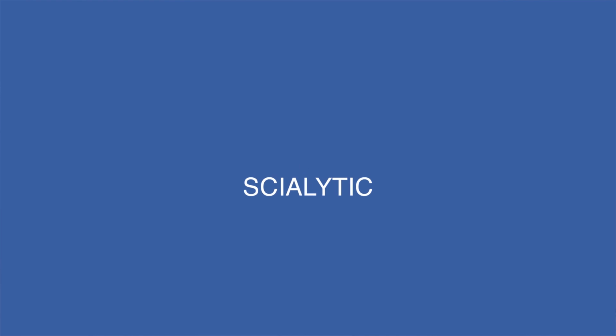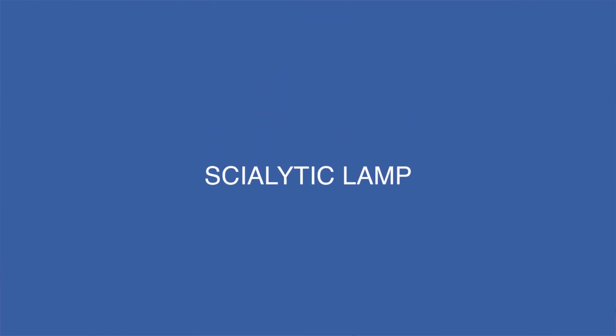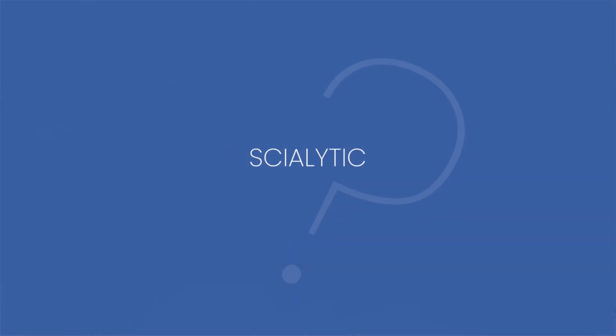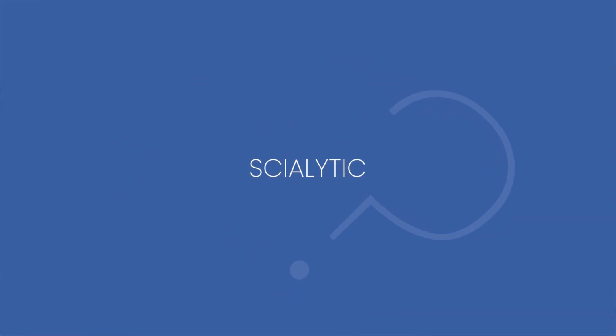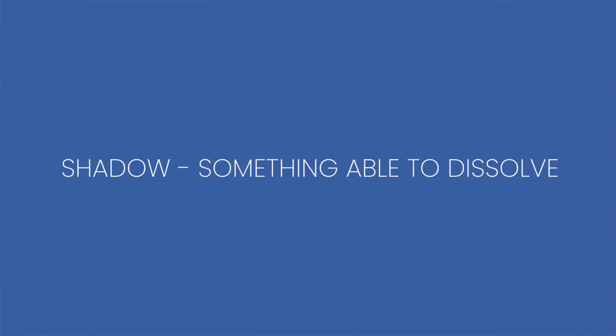Before addressing the history, however, I will allow myself an etymological analysis on the meaning of scialytic, because we refer to lamps as scialytic lamps, but what does scialytic mean? Scialytic is a compound word, made of skia and litikos. Skia is the Greek word for shadow, while litikos describes the ability to dissolve something. Putting them together, scialytikos identifies something capable of dissolving shadows.